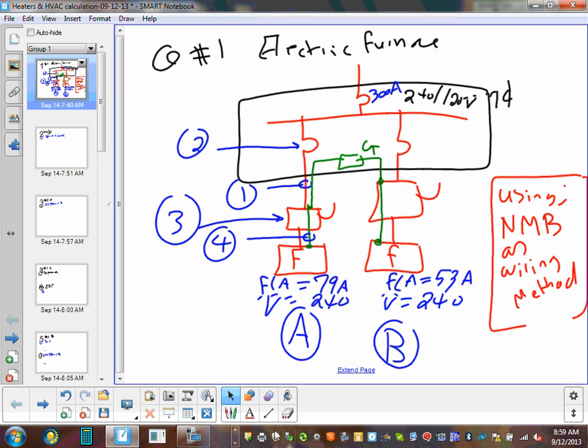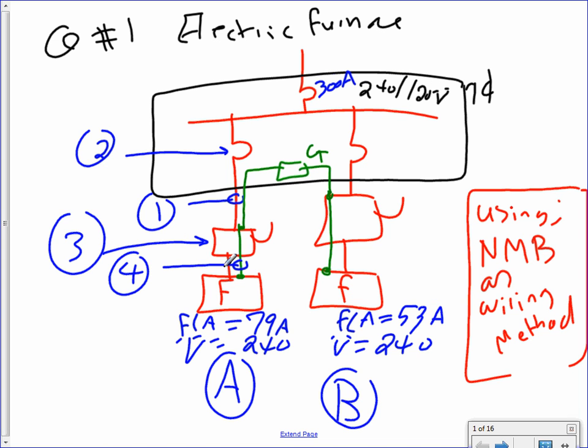This will be a good continuation of what we have done in the morning. Here's what I have. The first thing, since we're doing dwelling, let's focus. I'm using an NMB as a wiring method. Can you guys emphasize this one? It's so important, because I'm using an NMB as a wiring method, which forces you to use which column? The 60-degree column. If I use a different wiring method, you can go to the 75-degree column.